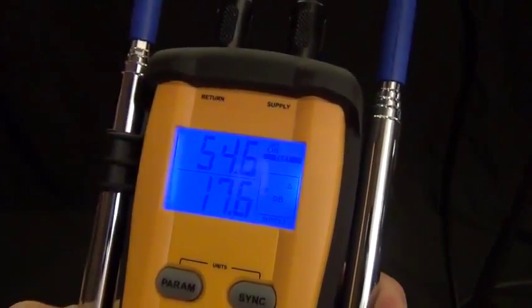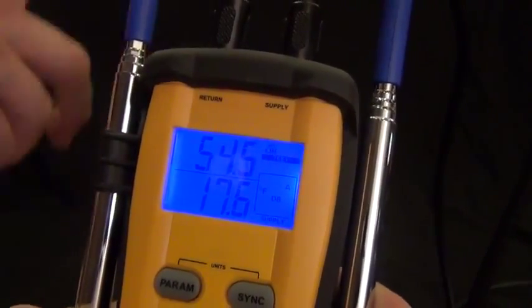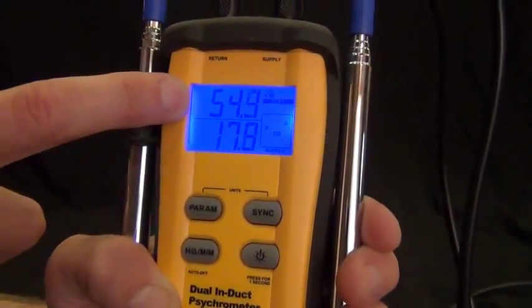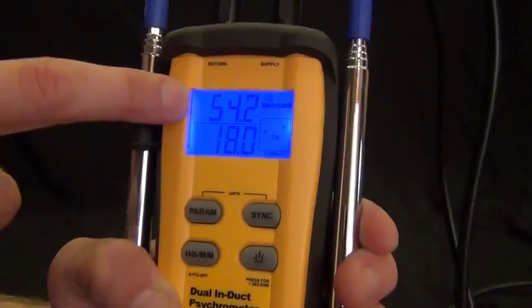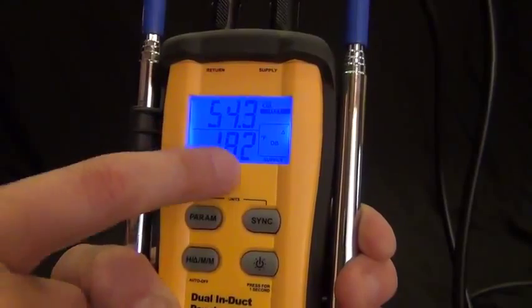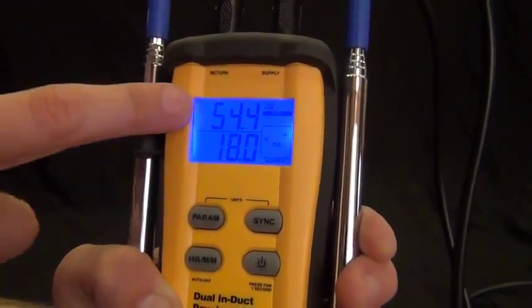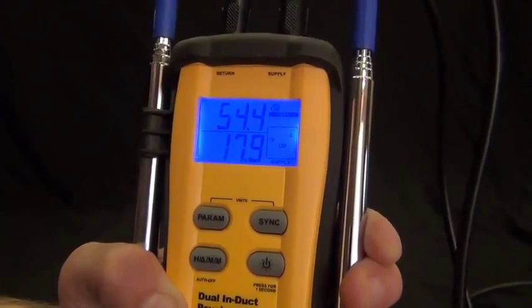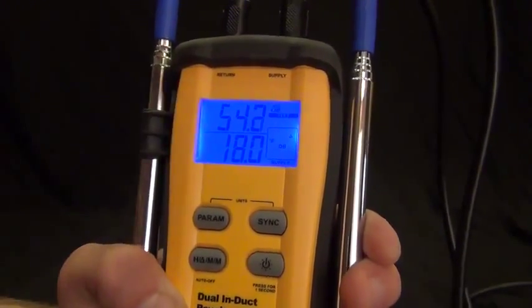So target evaporator exit temperature. And in this scenario I'm basically giving it a wet bulb and a dry bulb on my return side and it's telling me that my target evaporator exit temperature should be 54 degrees. And what this is saying is how far I'm off. So I'm 18 degrees above that 54 degrees, which in this case is about 73, 74 degrees in here. And so that would make sense.